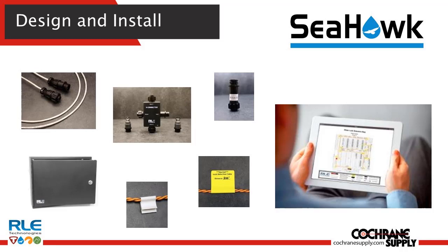So when you're coming into a zone and want to split out to another floor or another area, the guy in the middle there is called an X connector, which allows you to architecturally fit some of the different design options that exist. On the right there, it's called a weighted cable connector. Generally used when you're putting in series non-sensing cable, sensing cable, non-sensing cable, and sensing cable to make sure that you're getting a verified simulated resistance, so that if it did fall on the sensing cable on the first leg, within reason, that non-sensing cable is not counting towards the overall sensing length. So to ensure that from one zone to the next, in between the extensions, you may consider putting in a couple of these weighted cable connectors.